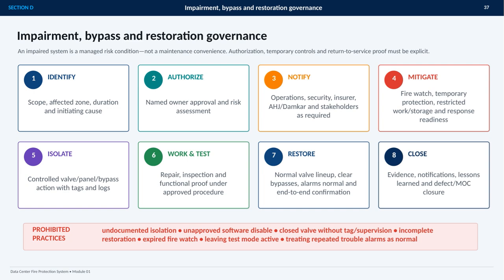Next, isolate the system through controlled valve, panel, or bypass actions, using tags and logs. Work and testing then proceed under an approved procedure, with repair, inspection, and functional proof. Restoration means returning valves to their normal lineup, clearing bypasses, confirming normal alarms, and completing end-to-end verification. Finally, close the impairment with evidence, notifications, lessons learned, and defect or management of change closure. The key rule is no undocumented or incomplete impairment. Prohibited practices include unapproved software disablement, untagged closed valves, expired fire watch, active test mode left behind, and treating repeated trouble alarms as normal.